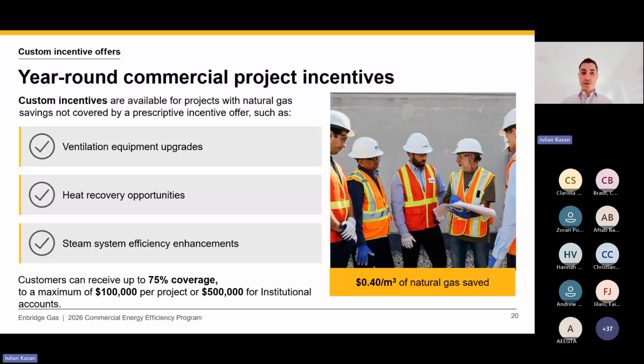Like I was saying, ventilation reduction projects, heat recovery opportunities, economizers, blowdown heat recovery chillers, steam trap replacements, steam pressure reduction, reducing boiler cycling, lead-lag setup on boilers - all these things are custom projects that we would incentivize. If it's going to save gas, we're willing to look at it, do a savings calculation, and probably give funding to it as well.